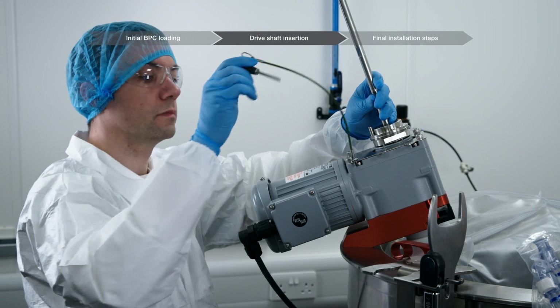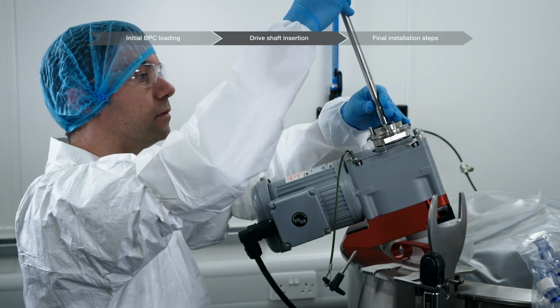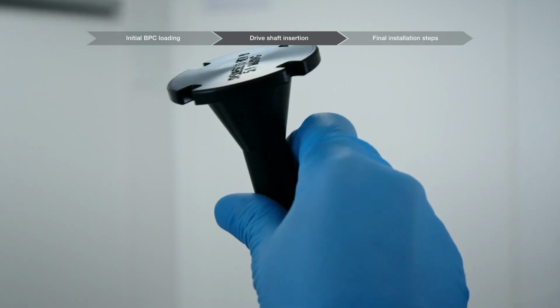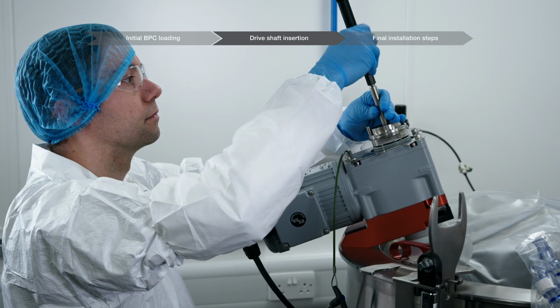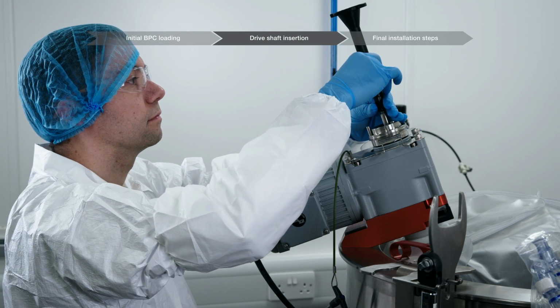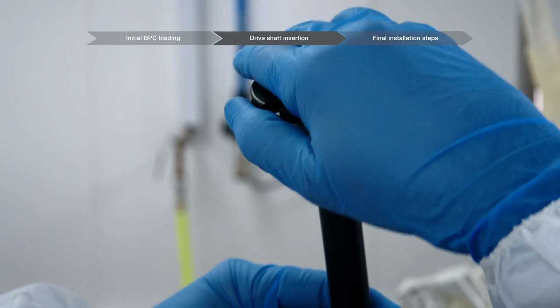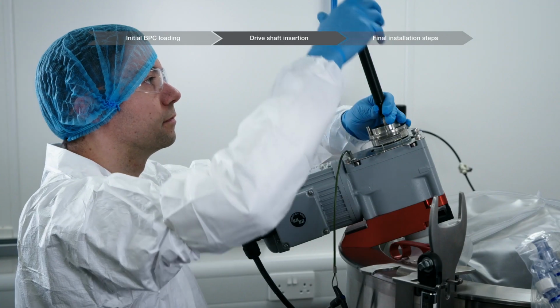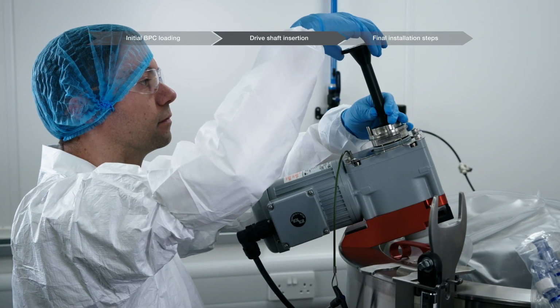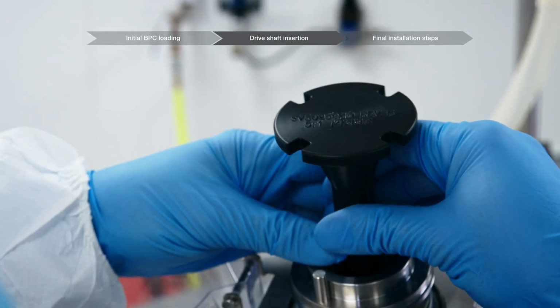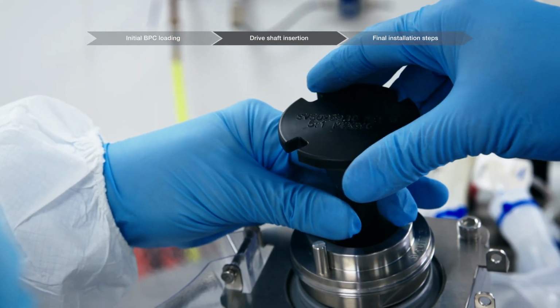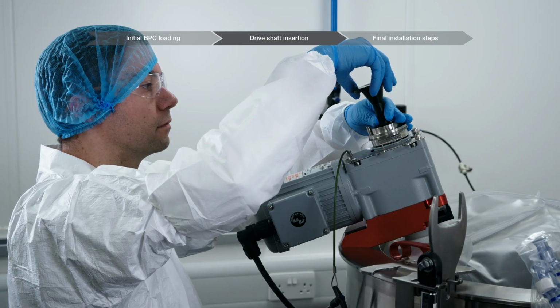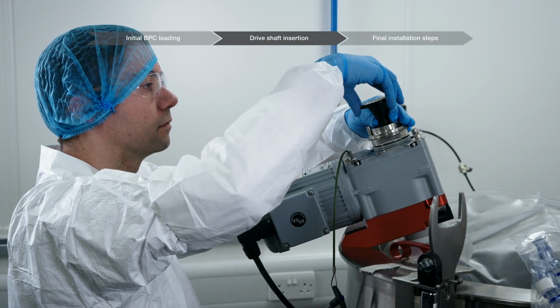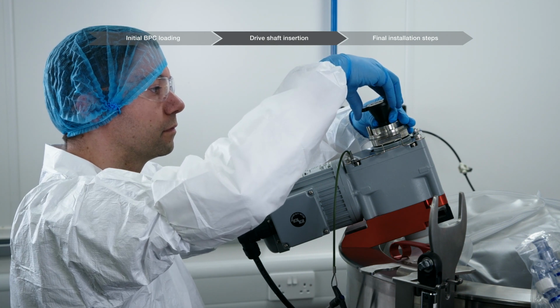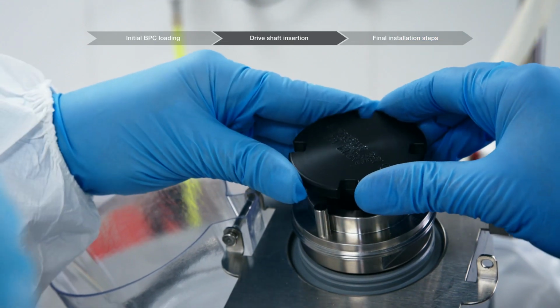Use two hands to load the drive shaft through the hollow pass-through of the motor assembly. Warning: do not use excessive force when inserting the shaft. Use a slight back and forth twisting motion to aid in insertion and avoid stretching the impeller tubing. If you feel pushback, you are using too much force. When approximately 51 to 76 millimeters, or 2 to 3 inches of the shaft remains, twist back and forth slightly to engage the impeller. When approximately 25 to 51 millimeters, 1 or 2 inches of the shaft remains, twist back and forth slightly to engage the bearing assembly.